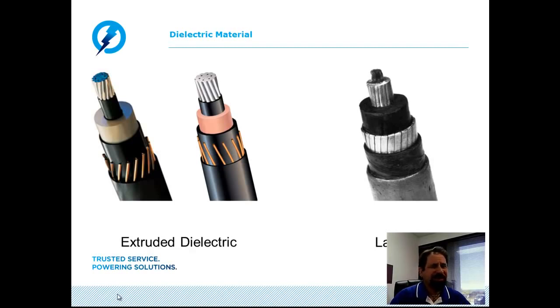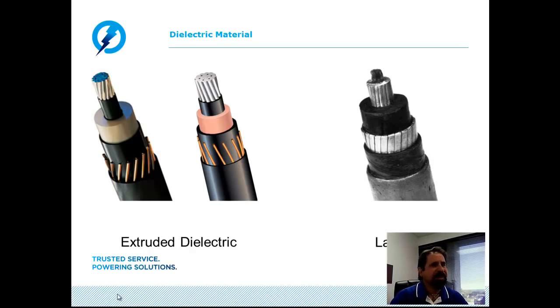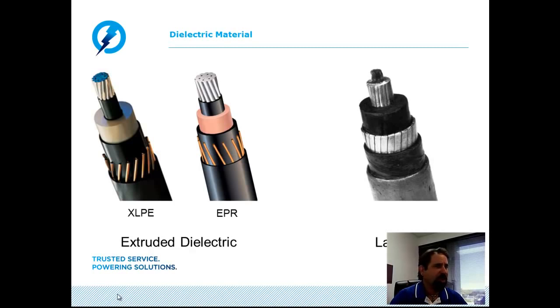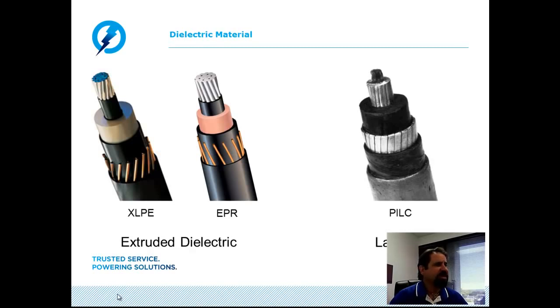There are two basic categories for cables: the extruded dielectric and the laminated style cable. Examples of extruded dielectric cables include cross-linked polyethylene (XLPE) or polyethylene (PE) style cables, and ethylene-propylene rubber (EPR). The paper insulated lead covered, or PILC, would be a representation of the typical laminated style cables.